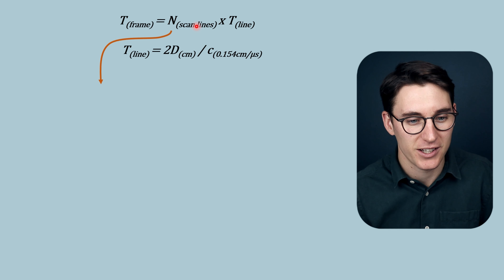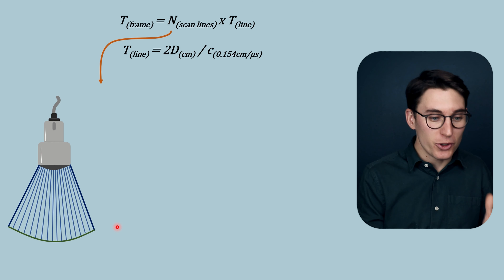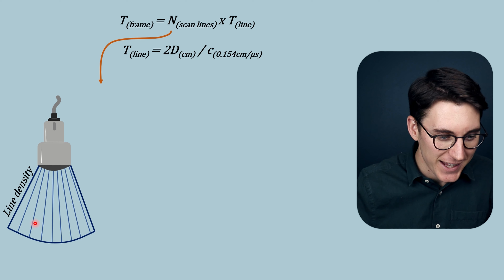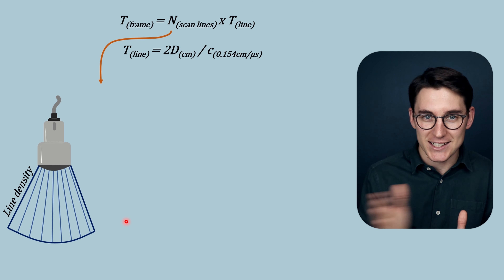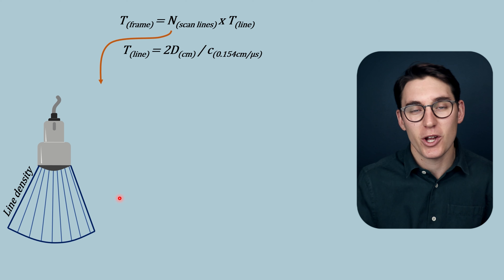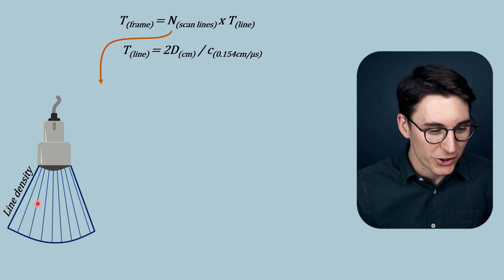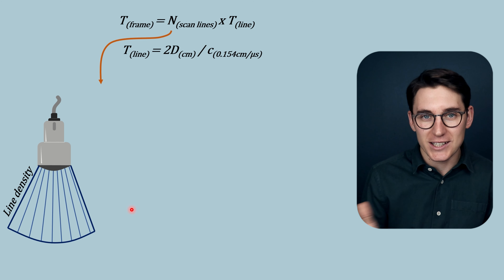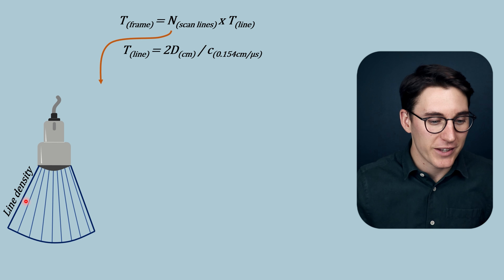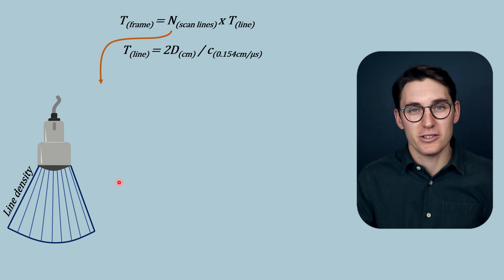We can alter the number of scan lines in two ways. The first is by reducing line density — reducing the number of A-lines taken within our field of view. The A-lines per centimeter decrease, line density decreases, and the time it takes to acquire a single frame decreases, giving us better temporal resolution and a higher frame rate. However, decreasing line density means we lose lateral resolution, as A-lines are further apart and some anatomy may be missed. Another term for line density is lines per degree — the number of lines within each degree of the transducer's field of view.